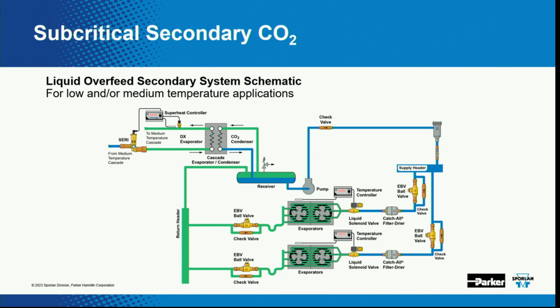In this case, this is all saturated - because this isn't an expansion device, so it's showing green here. That's probably a little confusing, but when that opens, you have liquid feed straight in, just straight liquid. As it's doing the heat transfer and the CO2 is picking up BTUs, it moves into a saturated condition, but it's never going to go above saturation. It goes back as saturated, and then you just separate the saturated liquid from the saturated vapor. That's my understanding of it.